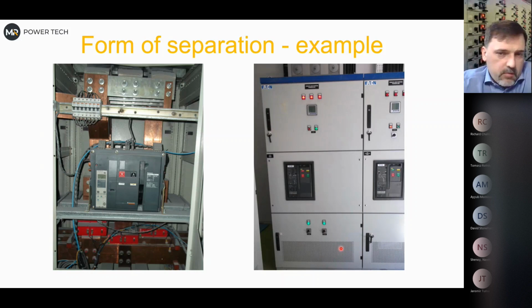And to be honest, I would expect that there will be a cable connection which is actually going from the top. There is a control panel, a control part of it, a compartment. It should be separated from the bus bars in this place. If you open the breaker, you see it's not easy to open. So probably if you open it, you have to see the bus bars and everything else. Sometimes they have covers in the front. And I think this is supposed to be the control compartment. But if you see 3 doors, you might expect something like 3A, 3B level, as a rule of thumb.